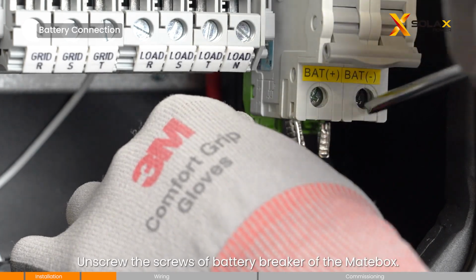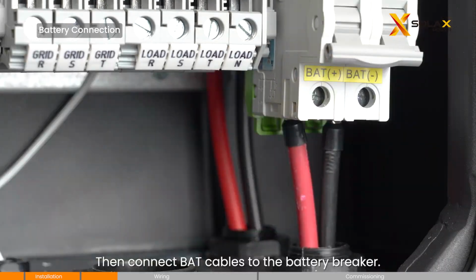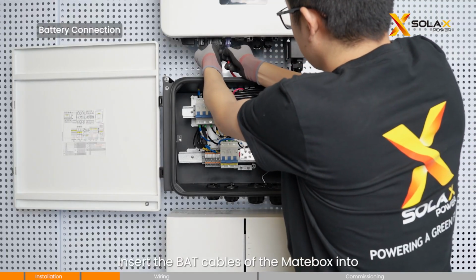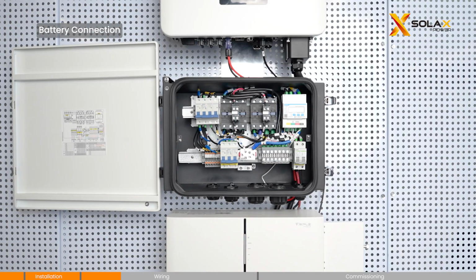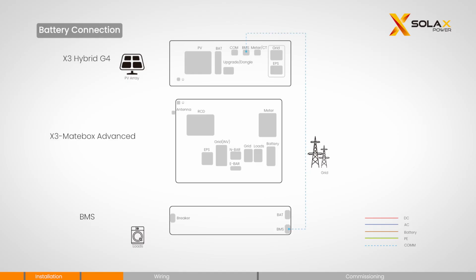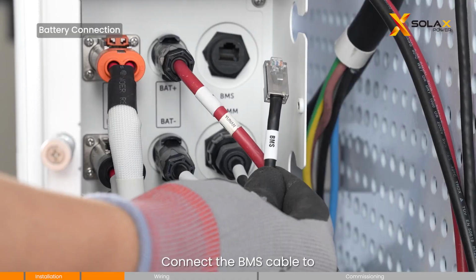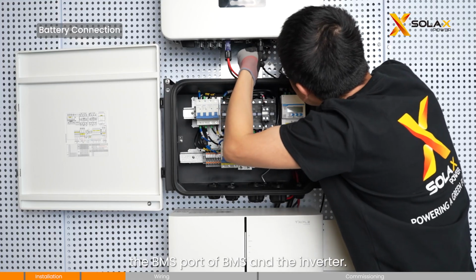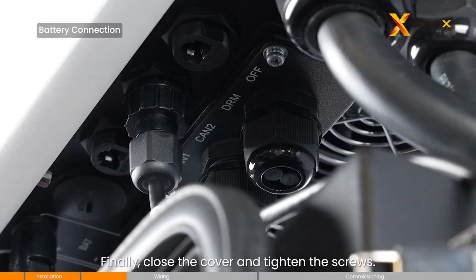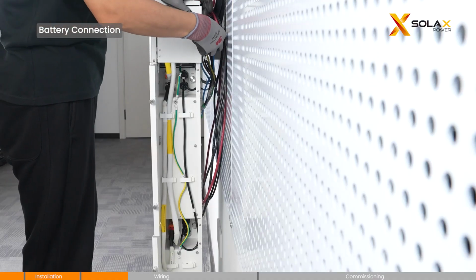Unscrew the screws of battery breaker of the matebox. Then connect bat cables to the battery breaker. Insert the bat cables of the matebox into the bat ports of the inverter. Connect the BMS cable to the BMS port of BMS and the inverter. Finally, close the cover and tighten the screws.